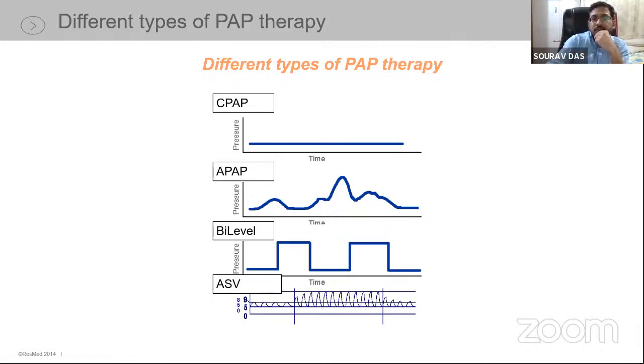There's something called the bi-level airway pressure, which gives one pressure level while the person is inspiring, and another pressure level when the person is expiring. So there are two pressure sets for every breath cycle instead of one pressure set as in the auto CPAP machine. There's something called auto BiPAP, which is not shown here, which does the same thing for each successive breath of the patient. So it varies the inspiration pressure and the expiration pressure with every successive breath.